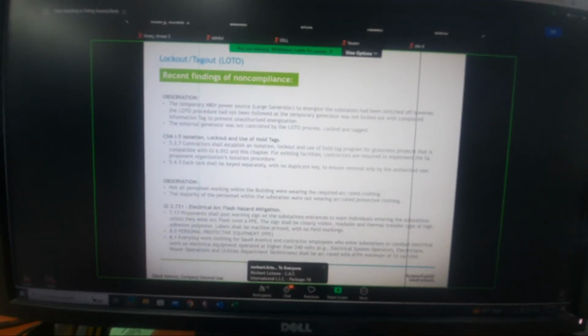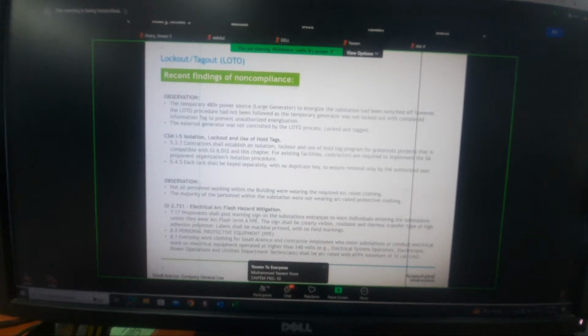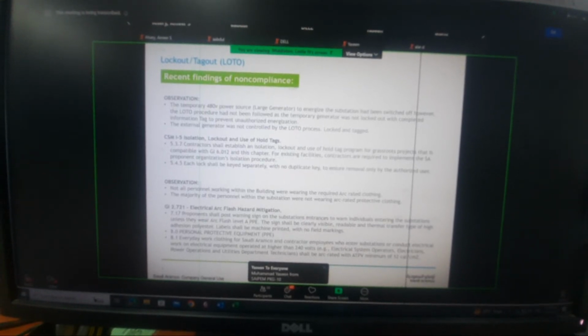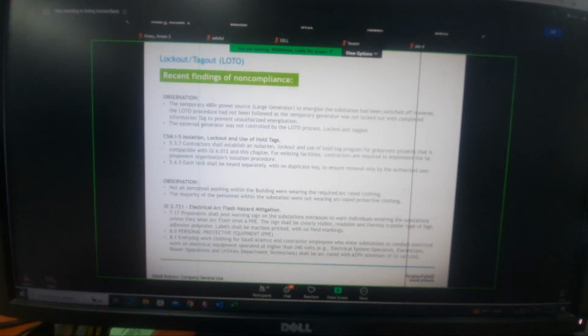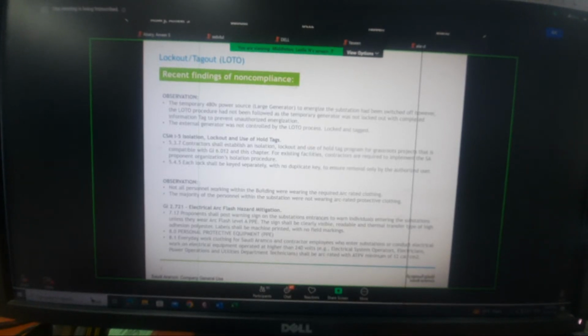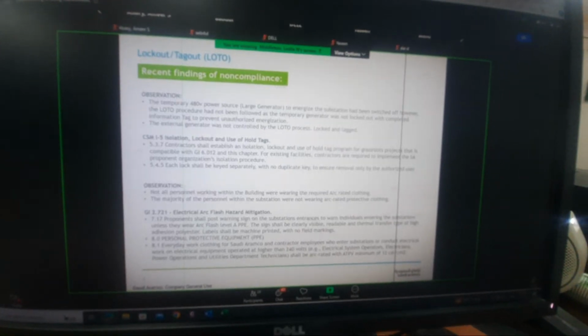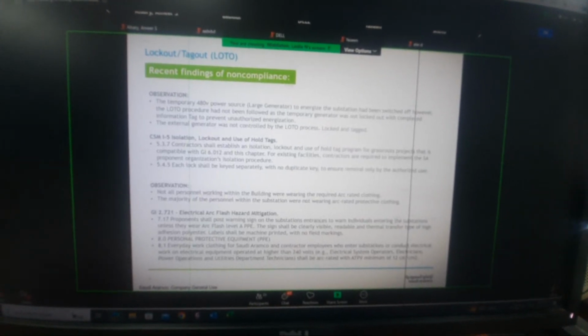So an example was, we seen energized control panels which are actually going through tests, but yet the generator external outside just had no additional signage on there. It just looked like a general generator, and it was not controlled by lock, so anybody could have come along, de-energize that, or any other way actually energize that generator. So we must include that as part of our controls, not just inside the substations.